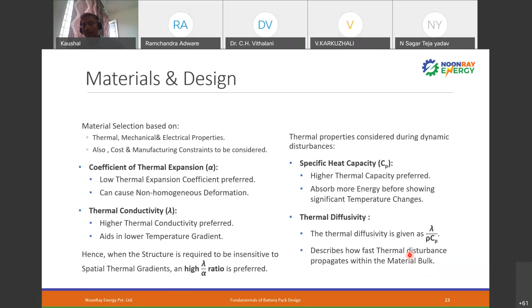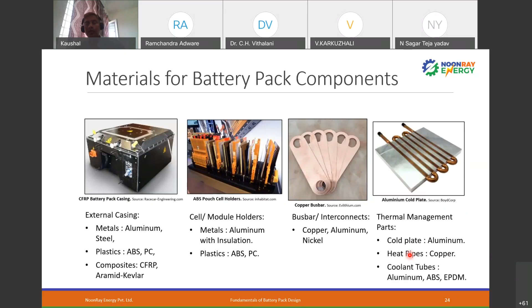So what are the things we are using for thermal design or battery pack design? Casing is basically ABS or CFRP. The cell holder, we generally use ABS. Bus bars, generally we use copper or aluminum. Cold plate, we use aluminum, copper, embedded tubes. Now, for thermal design, a summary: a good thermal design increases efficiency, gives longer life, and provides accident prevention and mitigation.